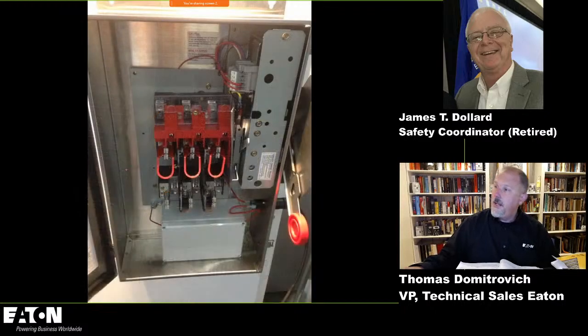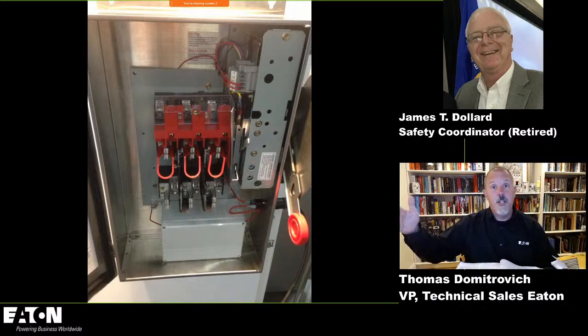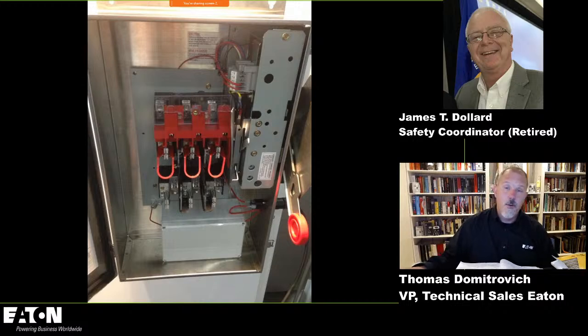Love that one. And this one here is a motor operated shunt trip switch that basically you can open remotely without opening the door. So from again remotely, and you could have something actuated like, I don't know, you can do ground fault protection. You can do some other method or whatever means that you want to automatically open this, as opposed to having somebody open it with their hand. So there's a lot of different options to get distance in and have it actuate based upon some other basis of condition. Or you could tie it to a door opening to the room and say, I'm going to kill this. If anybody enters this room for whatever reason, I'm going to kill the process that's going on in that room, or for whatever reason that you might have.